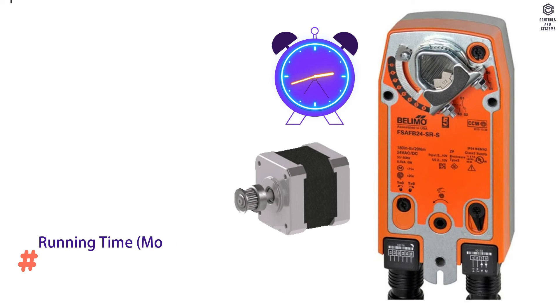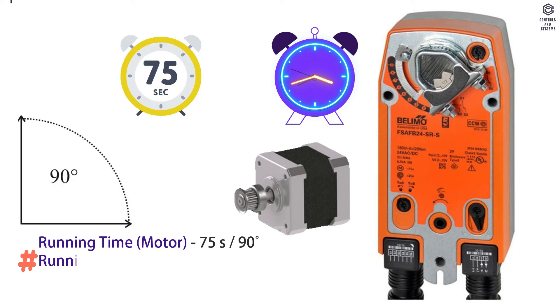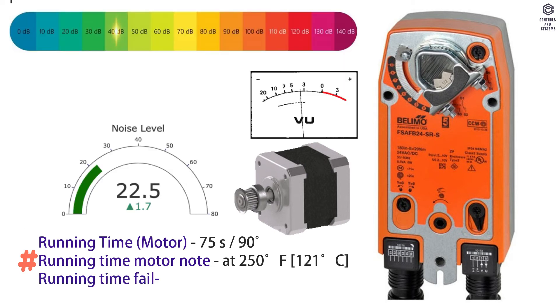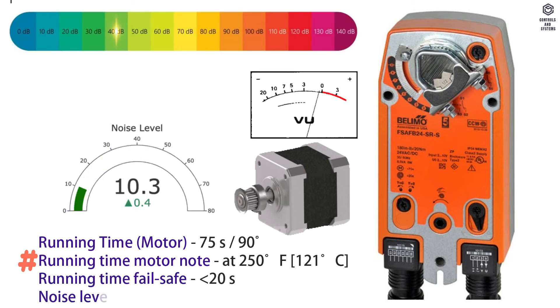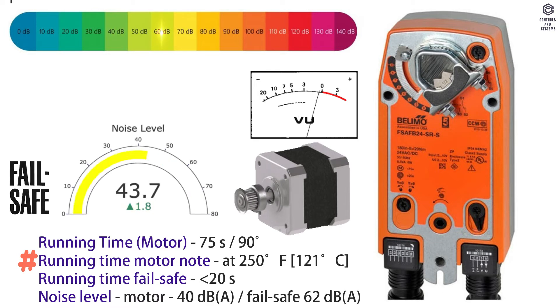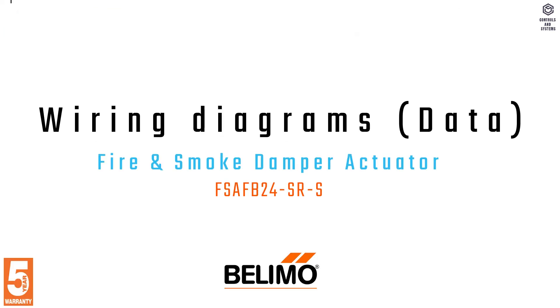Running time of motor is 75 seconds at 90 degrees. Running time failsafe is less than 20 seconds. Noise level in motor operation is 40 dB. Noise level at failsafe is 62 dB.